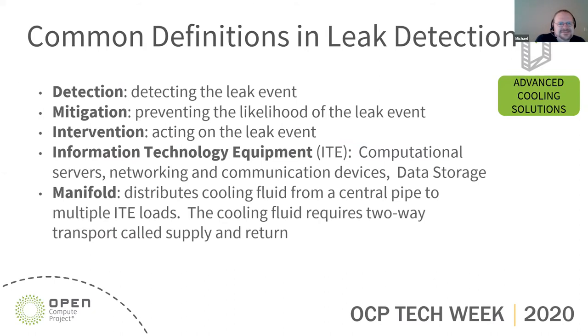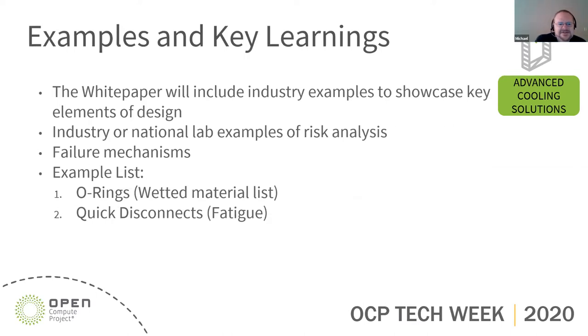Some common definitions: detection means actually finding the leak event; mitigation is preventing the likelihood of a leak event; intervention is acting on it — once a leak has been detected, what action do you take. IT equipment (ITE) covers computational servers, networks, communication devices, and data storage — the components we're worried about not getting wet. A manifold distributes fluid from a single input to multiple IT loads.